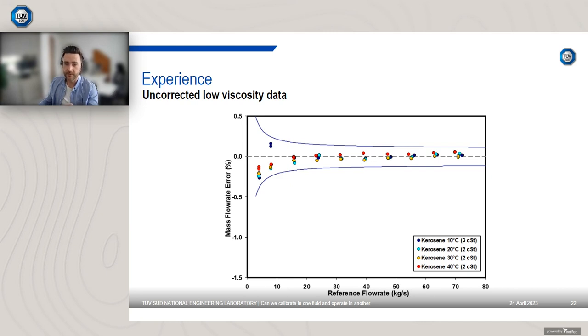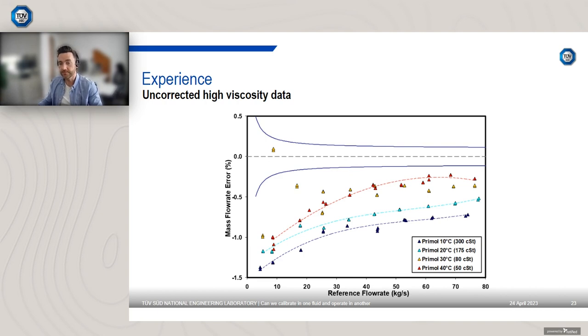This would be termed a light, low viscosity fluid. You can see I've overlapped the manufacturer specification, that's the dark blue lines, and all the data is well within the manufacturer specification. The dark blue points above the zero line at 10 kilograms a second are potentially the effect of the zero shifting the results, just at that one condition. Now that's the low viscosity fluid. We tested this exact meter, kept it in the same place, we didn't move the device, we simply changed the fluid. From one day to the next we can change the test fluid. So the results are well within specification.